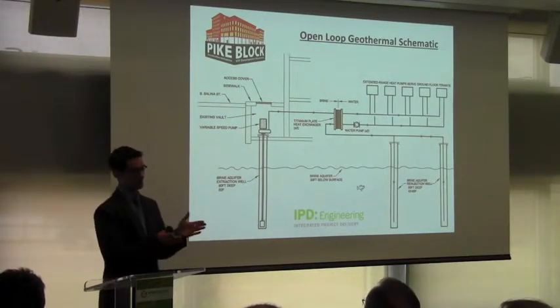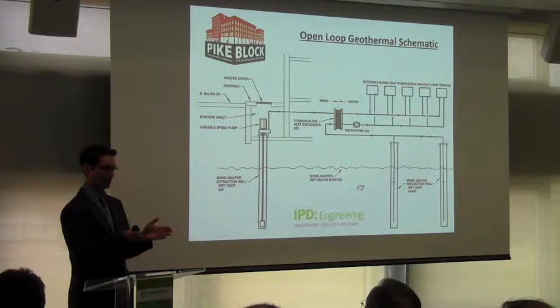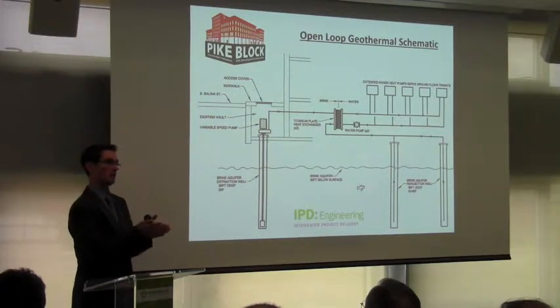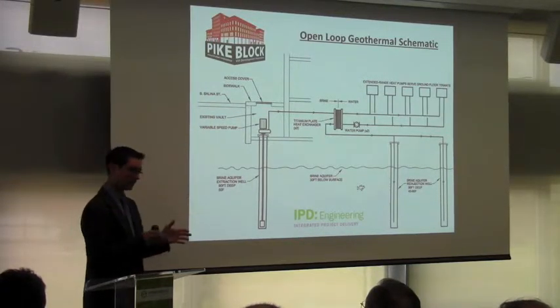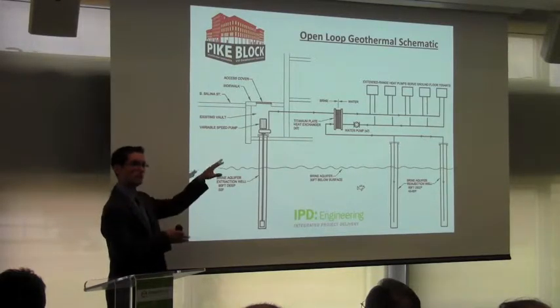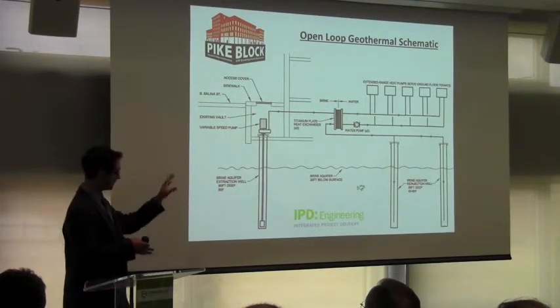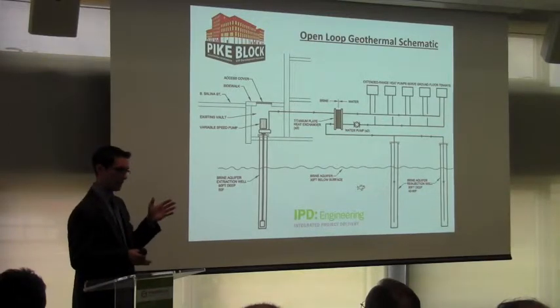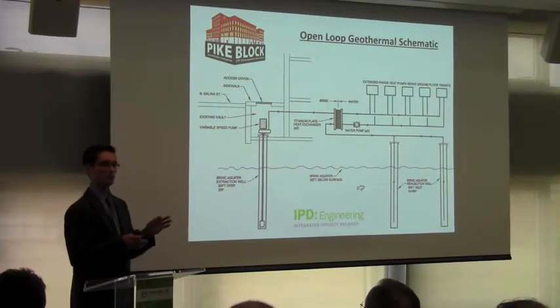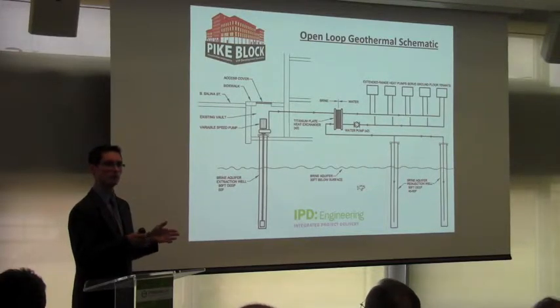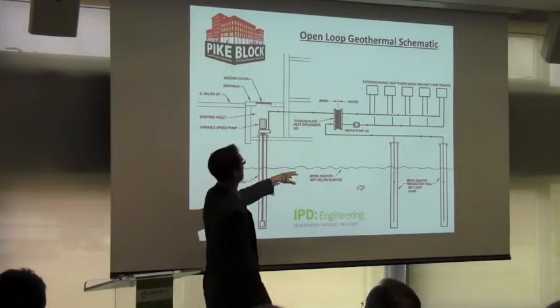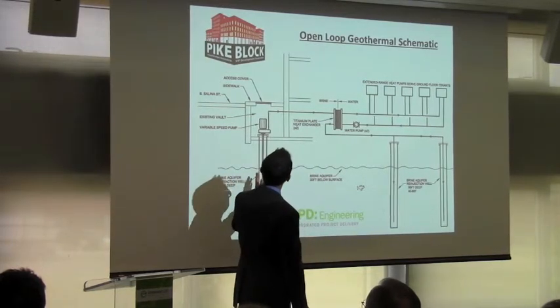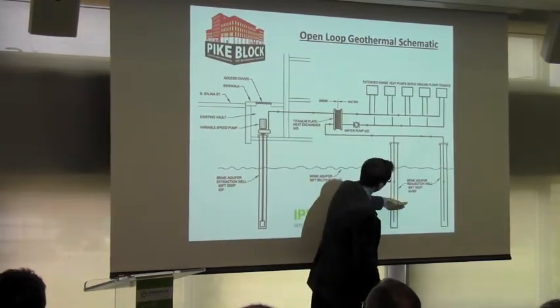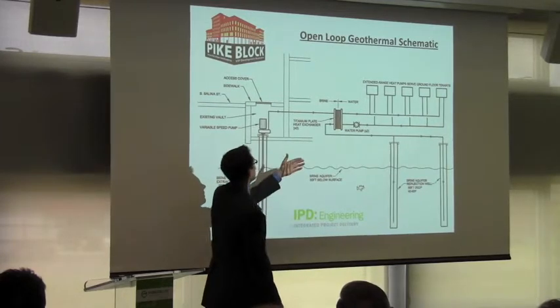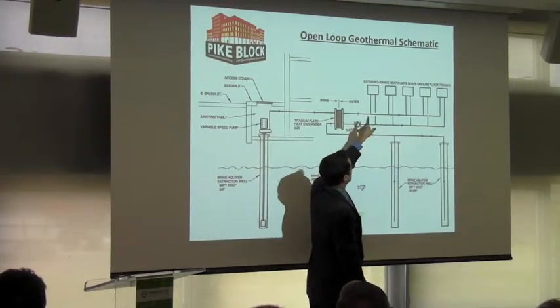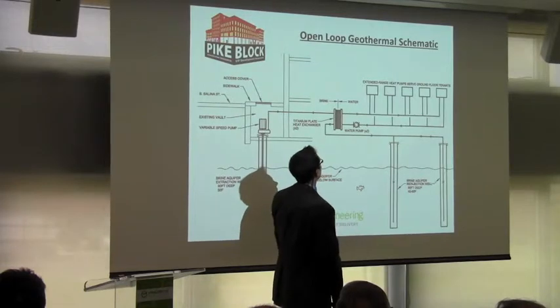The plate and frame heat exchanger consists of 80 to 100 plates that are very thin, very close together. On one side of each plate there's the brine, on the other side there's the water for the heat pump. This device allows us to keep the brine and the water very close in terms of their temperatures, only 1 or 2 degrees apart from each other. So a lot of heat transfer can happen in a plate frame heat exchanger. Brine comes up, comes out, gets pushed back into our reinjection wells. On the other side, the water just flows around in a circle through the heat pumps.